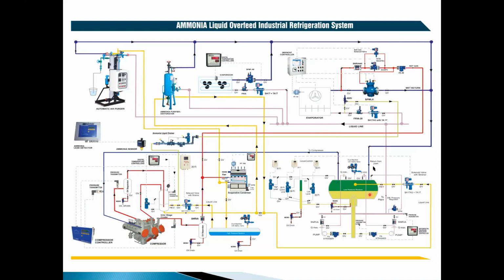In this LP vessel, when the liquid ammonia comes in, the liquid falls down, goes back through the pump into the system, and only gas gets separated and goes to the compressor. As I was telling you, we can have multiple temperatures in different applications depending on your requirement. You can have +5 degrees to -40 degrees. For those applications, you can have back pressure regulating valves.